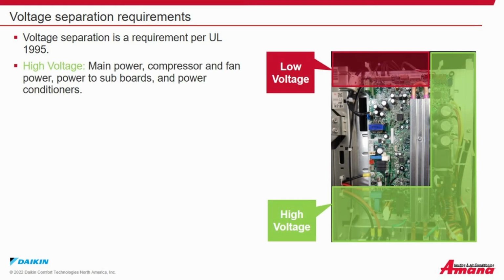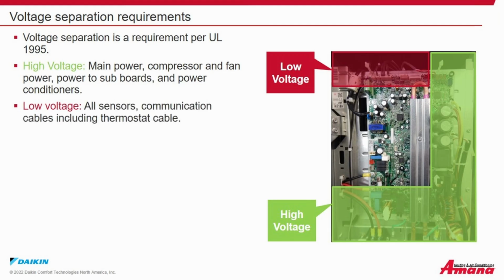Voltage separation requirements. Voltage separation is a requirement per UL 1995. The diagram on the right shows high voltage, which is shown in green, which is main power, compressor and fan power, power to the subboards, and power conditioners. Low voltage, represented in red, are all sensors, communication cables, including thermostat cable.